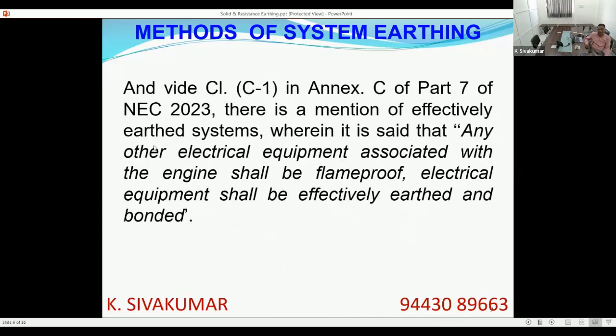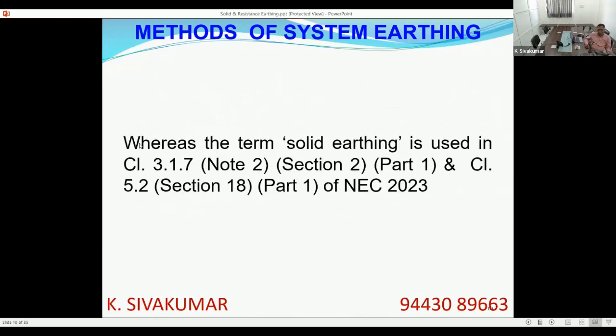And one more place in NEC, Annex C to Part 7, it is for generators. It says generator equipment, electrical equipment shall be effectively earthed. But per se, no standard in India has precisely explained what is effective earthing and what is non-effective earthing. Again, NEC mentions solid earthing in many places rather than effective earthing. It also mentions solid earthing in a couple of clauses.